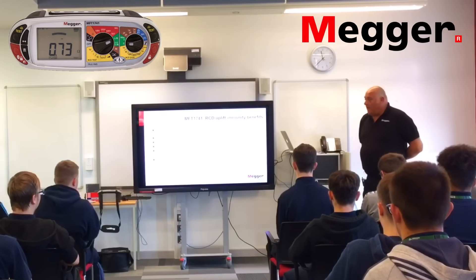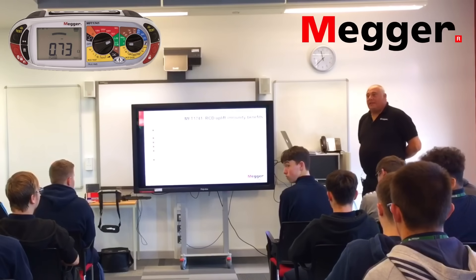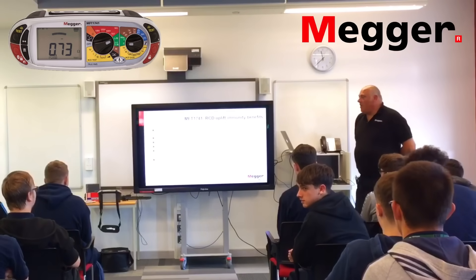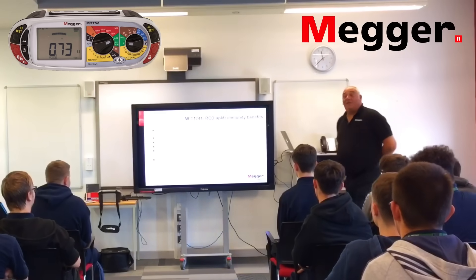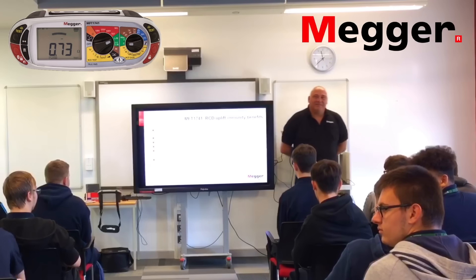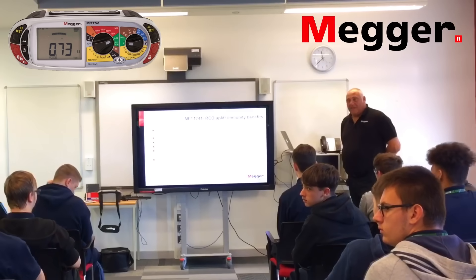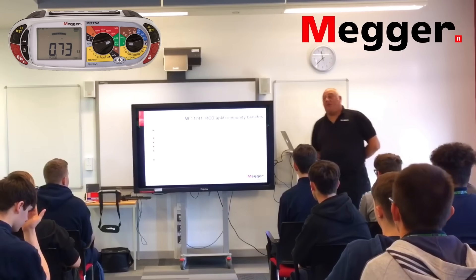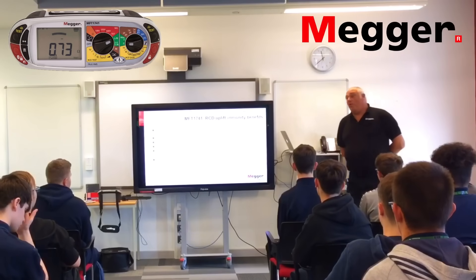Something I thought I'd put on for Gary — stand up and take a bow, sir. What does it say at the bottom there? No need to continually null out lead resistance. All the multi-function testers from Megger — once you've zeroed out the leads, you don't need to do them again, unless you're putting new leads in. Even if you turn the meter off, take the leads out and put the plug in — which internally is already zeroed out — put the leads back in and you don't need to zero them out.